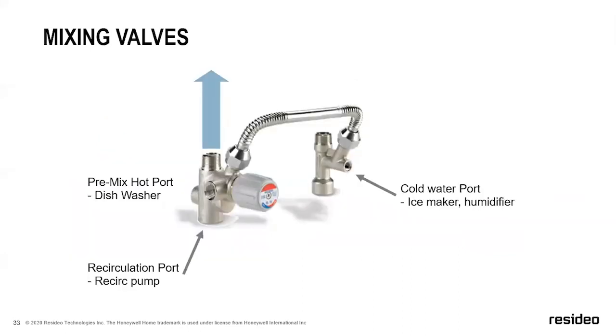How it works. So you've got on the left side, that's where your hot goes in, and it gets mixed coming out of the top there where you see the blue arrow coming up. On the right side, ports are cold. There's a jumper bar between with flare fittings, where the mix is. The cold water is going to come from the right, go into the left, mix with the hot from the tank and go up to the facility. And we've got ports. So on the right, we've got a 1/4-inch cold water port. You can utilize that to go to an ice maker or humidifier, maybe a refrigerator for cold water coming out of your fridge. On the left, we've got a pre-mix hot port. So if you've got 140 degrees coming out of your tank, you can take that right to a dishwasher.